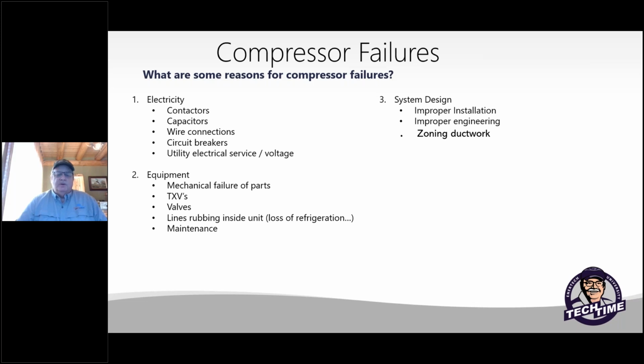Ductwork zoning is another interesting one. If you had a two-stage compressor system, and I would say one of the zones is only partially open and the compressor is running full speed instead of dropping into part load, it can create some issues of flooding refrigerant back to the system too as well. So always make sure your zoning programming in the zone panel is done properly according to the equipment that you have.